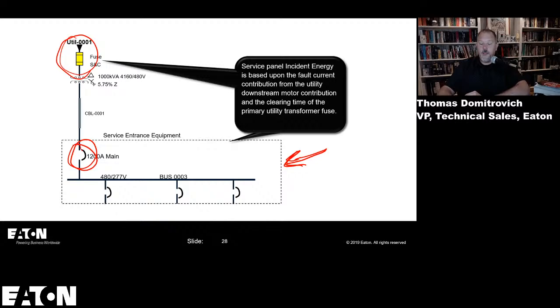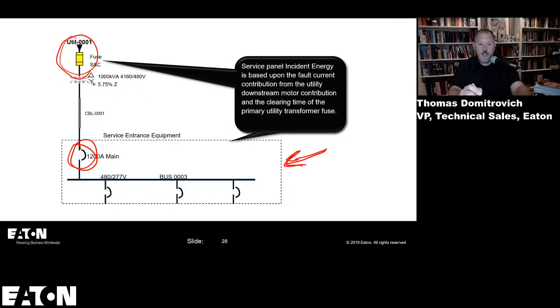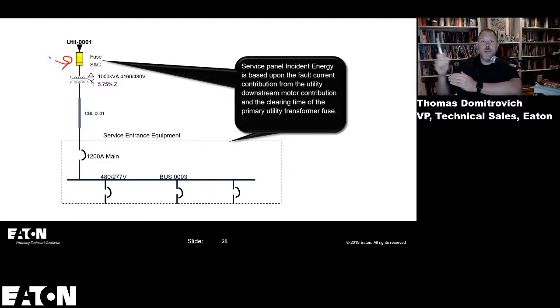And if you think about the issue that you have in this case from sizing this primary overcurrent device, you are increasing the size over the full load amps. You're not sizing it directly for the full load amps of the transformer. You're actually increasing it to a larger value. And the primary reason, no pun intended, is because of the inrush current of that transformer. And what happens is you're putting a larger overcurrent device in.